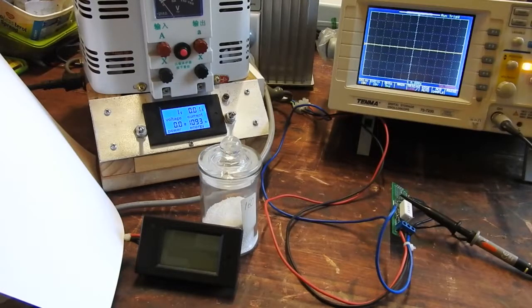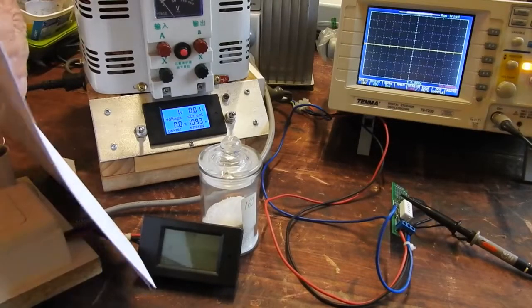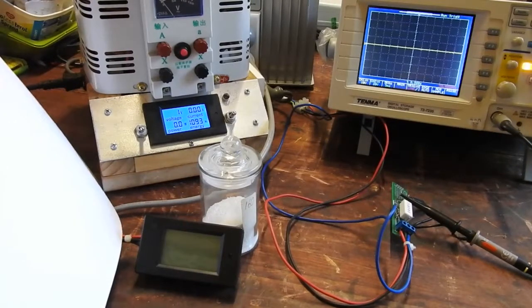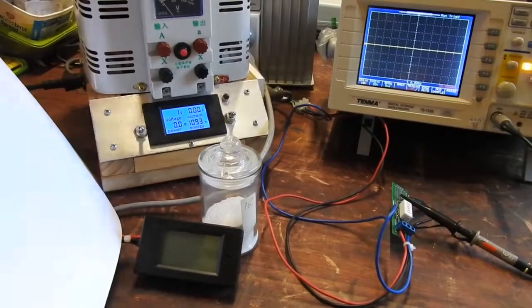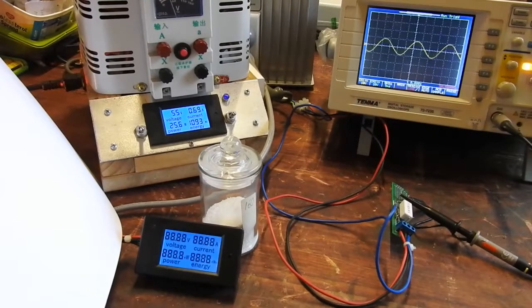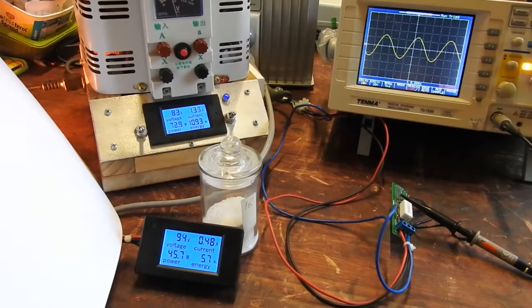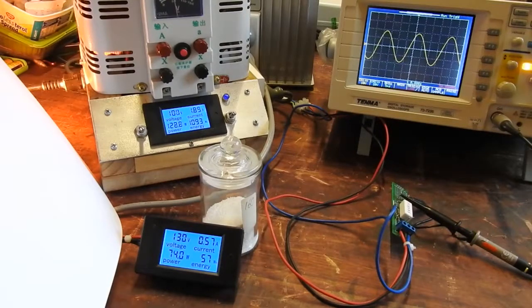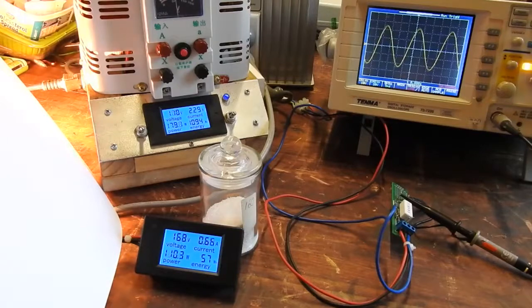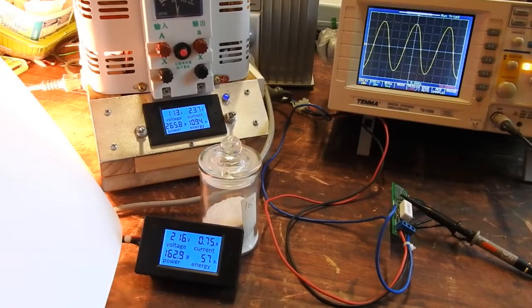And connect in this guy, which is 150 watts, so that'll take us to, what's that, 205 watts, something like that, and the transformer is rated at 275 VA, so we're getting close to its rated limit. So we'll see if the waveform's any worse with more load. Winding it up again. We've got to go more than 80 volts before we hit our resonant point, resonant transformer activity. Still more. Still only getting 130 out for 100 in this time. And there we hit it, 110 volts, and we're starting to get decent output. And the waveform's not bad. Winding up further.